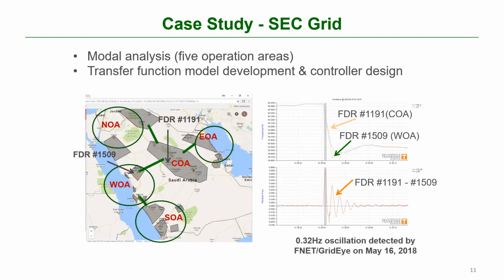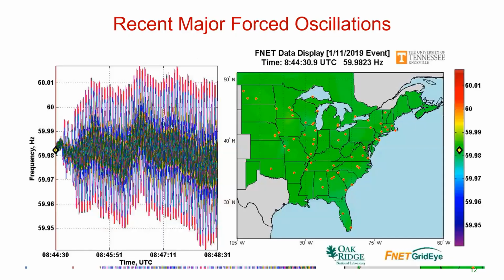We also have ongoing work with Saudi. They have an issue that's not just oscillation, but a stability issue caused by oscillation, because their out-of-step relay kicks in and separates the grid between source and load, causing blackouts in some regions. That's another application using time-synchronized, or phasor, monitoring to deal with this.